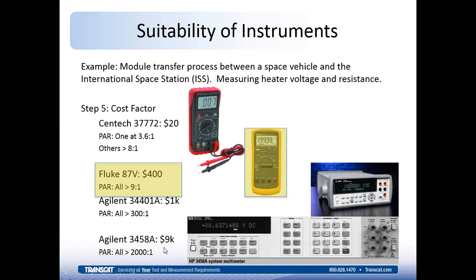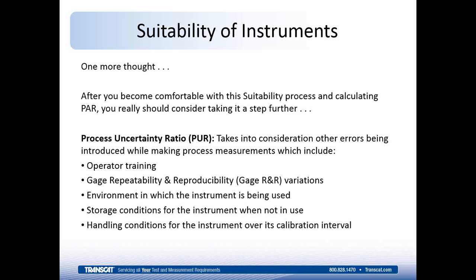Also, the environment in which the instrument is being used. If you have a very sensitive instrument that requires tight controls on humidity or temperature or vibration or lighting, you've got to take that into consideration. And if you don't have those controls in place for the environment, does that throw the readings off? Does that give you a false indication? Storage conditions of the instrument when it's not in use can affect the accuracy of an instrument or the ability for it to make its correct measurements. And then, of course, how you handle the instrument during its use over its calibration interval, in between times that it's checked for its accuracy.